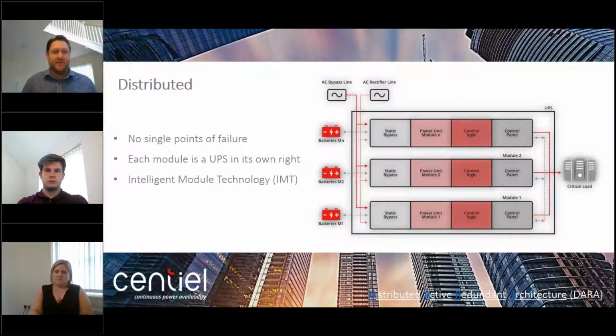The philosophy behind the distribution of the system is to replicate every single component within the UPS. When we say within the UPS, we mean UPS modules - multiple modules within the system make up a total UPS. Every module has a static inverter, a static bypass switch, a rectifier, a CPU system, control logic, control panel, physical control wiring, and so on. The reason behind this is to remove any single point of failure within the system.